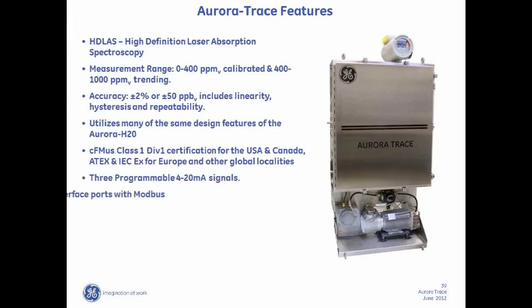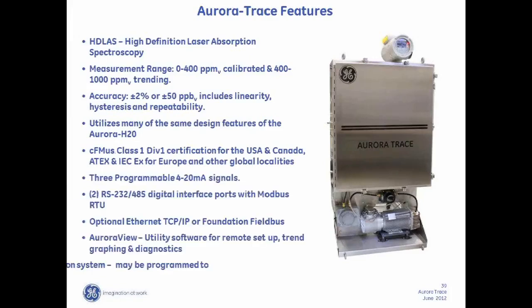For ultra-low levels, we have the Aurora-Trace, and that was launched last year. So the standard Aurora goes down to about 5 parts per million as its lower detection level. And this Aurora-Trace is able to go down to virtually pretty close to 0, but no system gets to 0. It will go down to 50 parts per billion fairly consistently. And one of the ways it does that is there are really 2 aspects that enable it to give what we call high definition laser absorption. One is we apply a vacuum to it, and the vacuum has the opposite effect as pressure broadening. We call it pressure sharpening.